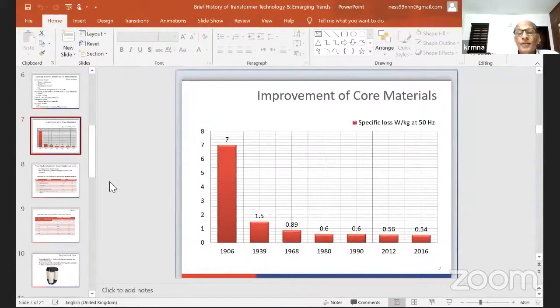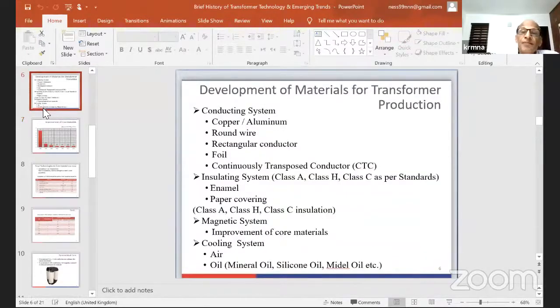Before proceeding further on magnetic material, I would like to mention that silicon steel, which we call CRGO steel - cold rolled grain oriented silicon steel - has been in use for many years. This material has improved because of improvement in grain orientation, so the best material today gives like 0.6 or 0.5 watts per kg.